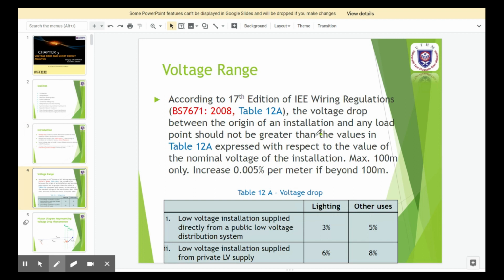So this is about the voltage range. According to the 17th edition of the IEE wiring regulations, BS 7671:2008 Table 12A, the voltage drop between the origin of an installation and any load point should not be greater than the values in Table 12A. This is Table 12A for the voltage drop, expressed with respect to the nominal voltage of the installation. Maximum 100 meters only. If more than 100 meters, we have to consider 0.005% per meter for the voltage drop.